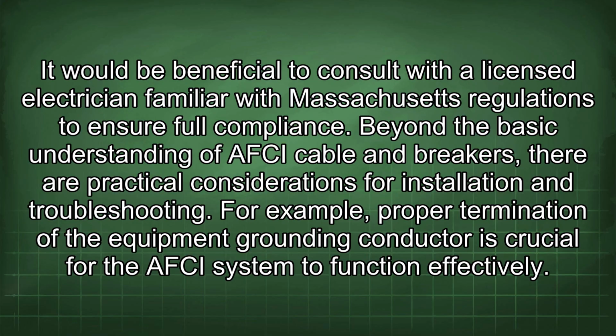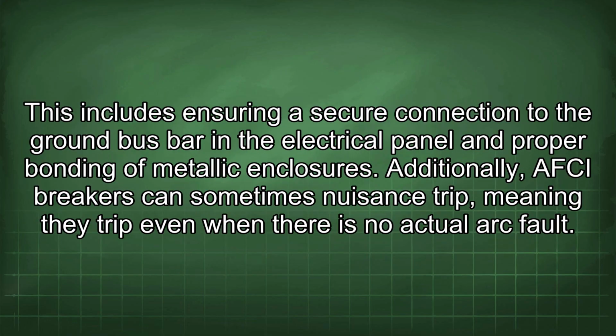Beyond the basic understanding of AFCI cable and breakers, there are practical considerations for installation and troubleshooting. For example, proper termination of the equipment grounding conductor is crucial for the AFCI system to function effectively. This includes ensuring a secure connection to the ground bus bar in the electrical panel and proper bonding of metallic enclosures. Additionally, AFCI breakers can sometimes nuisance trip, meaning they trip even when there is no actual arc fault.